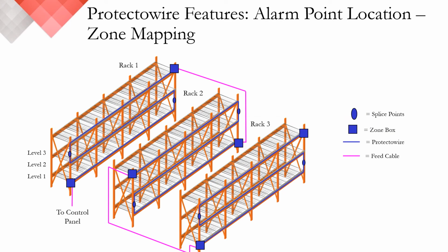This is an example of a simple facility zone map for a refrigerated or freezer warehouse with rack storage. One of the largest benefits to having Protectowire within the racks is the fast response provided through the proximity detection. Once the detector activates, knowing where the overheat is located within a facility is very beneficial. Zone maps can be a simple graph or table with rack numbers and distance markers, or they can be a really sophisticated annunciator. Regardless, the linear heat detection technology has the ability to provide hotspot location, so having even a basic zone map can be very helpful for locating an alarm as well as troubleshooting any short faults.